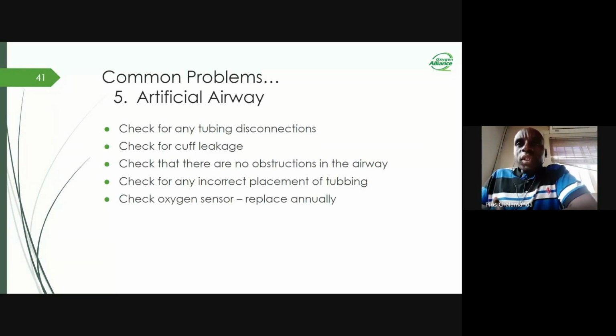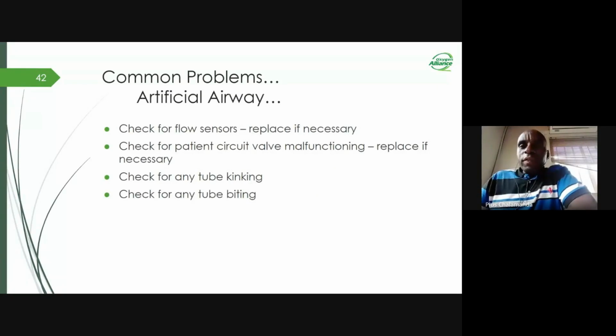Check for oxygen. Check the oxygen sensor. Check it and replace annually if possible, as I've already said before. Check the flow sensors and replace if necessary. Check for patient circuit valve functionality and replace where necessary. You can also check for any kinking within the tubings and correct them if they are present. You can also check for the presence of any bitings that may cause some leakages within the patient circuit.